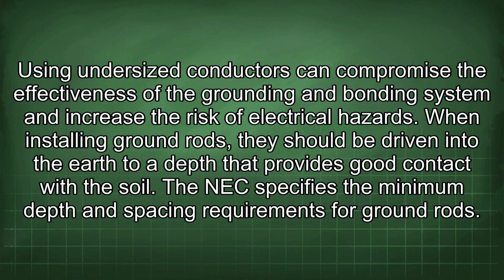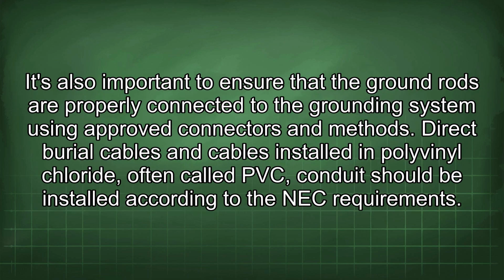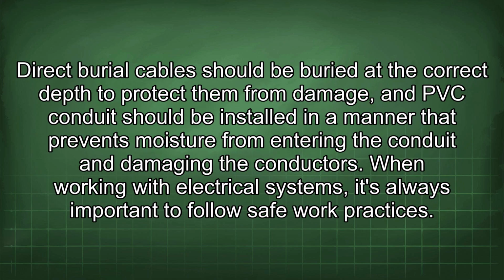When installing ground rods, they should be driven into the earth to a depth that provides good contact with the soil. The NEC specifies the minimum depth and spacing requirements for ground rods. It's also important to ensure that the ground rods are properly connected to the grounding system using approved connectors and methods. Direct burial cables and cables installed in polyvinyl chloride, often called PVC, conduit should be installed according to the NEC requirements. Direct burial cables should be buried at the correct depth to protect them from damage, and PVC conduit should be installed in a manner that prevents moisture from entering the conduit and damaging the conductors.